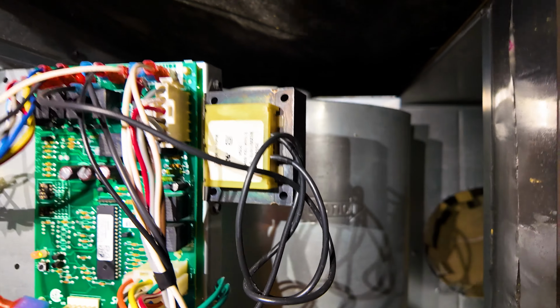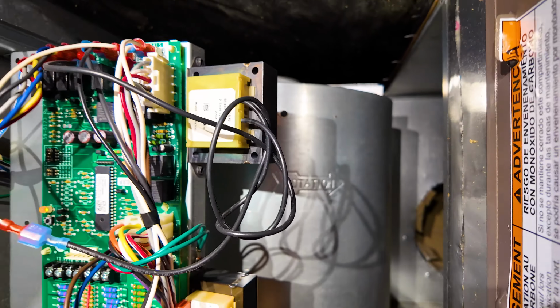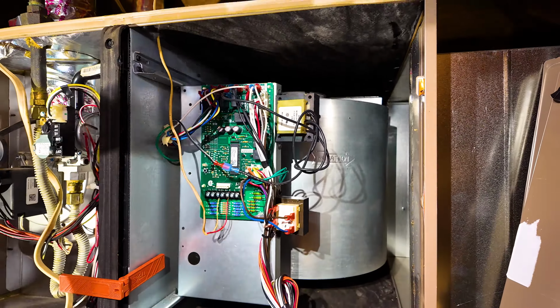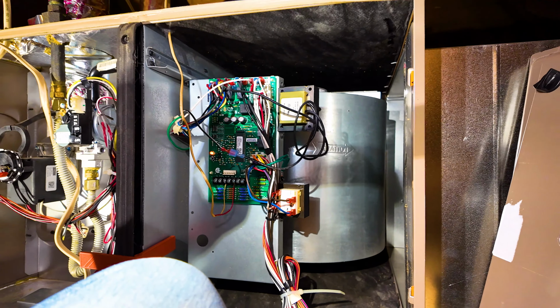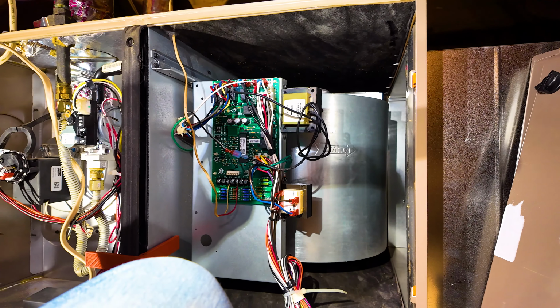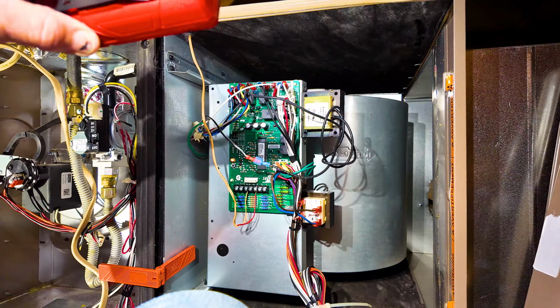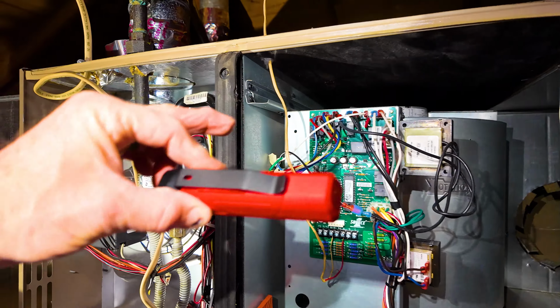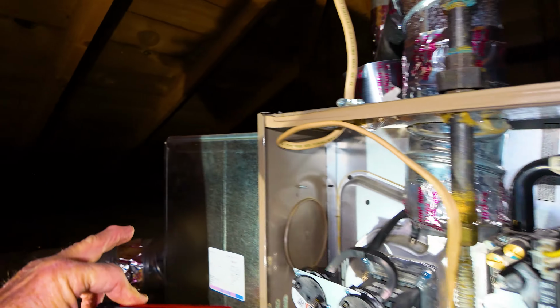Once the firebox heats up for 20-30 seconds, whatever it takes for the burners to get the system hot, then the big blower fan motor comes on here, which is what circulates the air through the house. So that way it doesn't blow cold air. It waits till the furnace heats up, the burners heat up the heat exchanger for a little while, and then when it's a certain temperature, it kicks on the big blower fan, as you see in there, behind there. That's what sucks the air in through the air return and then blows it out. It blows it across the heat exchanger over this way, and then goes out through this into the ductwork of the house.